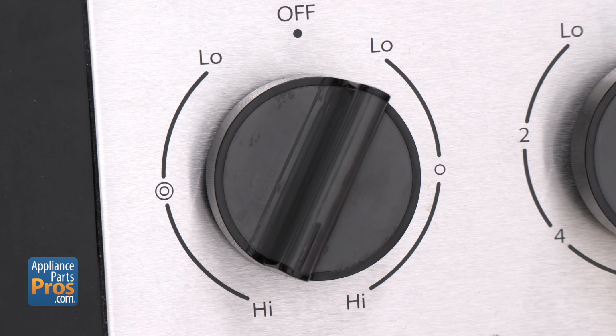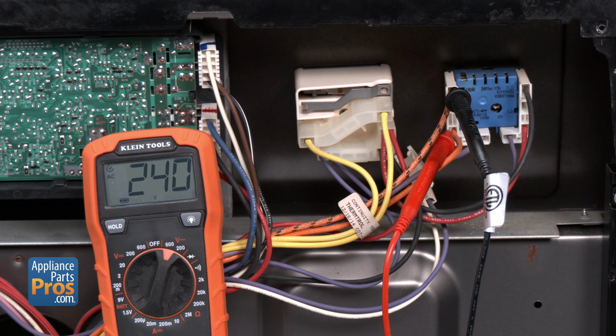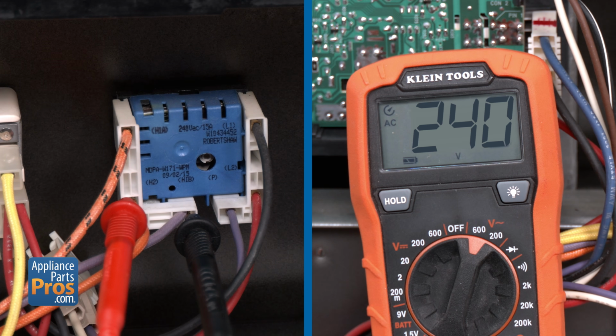Now rotate the burner control switch to the dual high setting. Place one probe on the orange wire at terminal H2 and the other probe on the orange wire with a black stripe at terminal H1A. Repeat the test between H2 and the orange wire with a white stripe at terminal H1B. You should see 240 volts AC at each point. If either reading is missing, the infinite switch has failed.